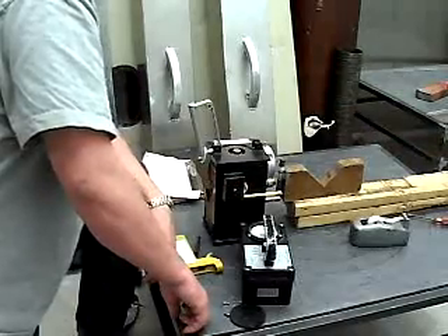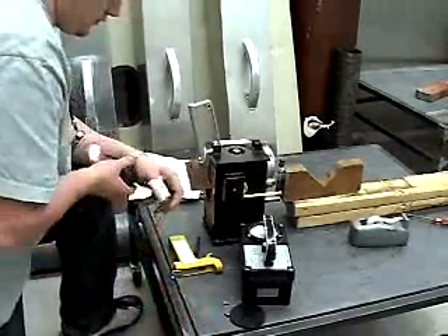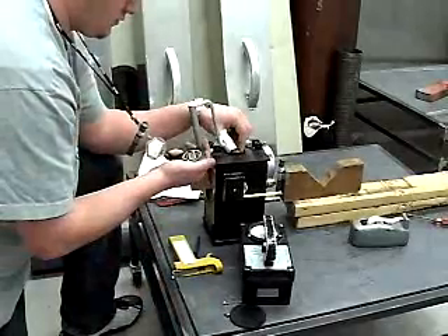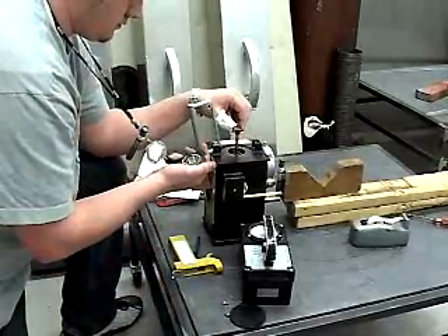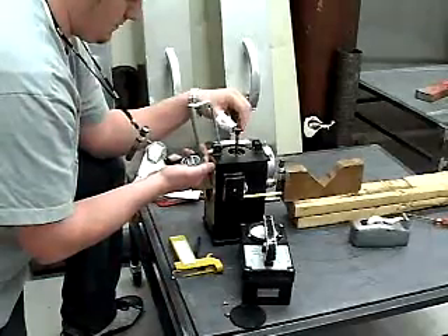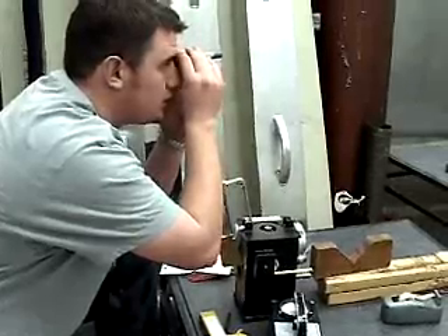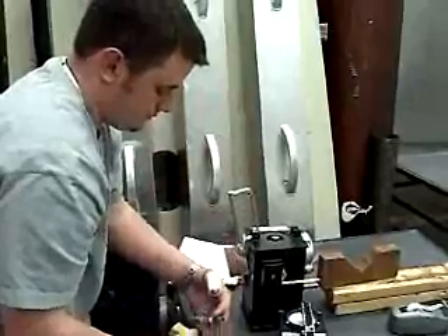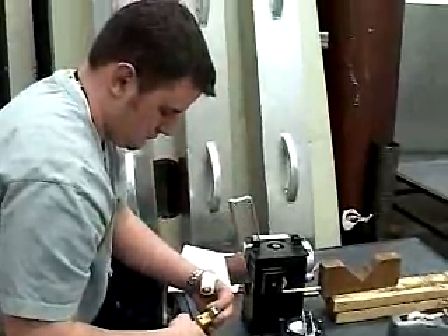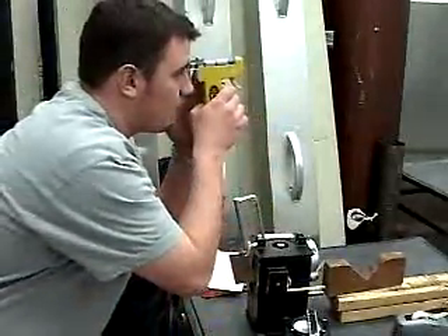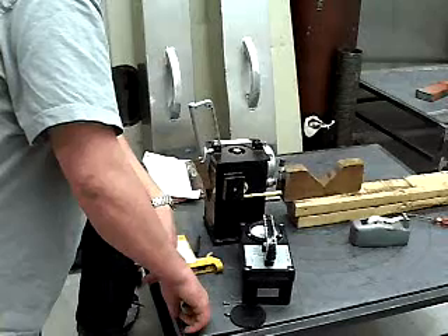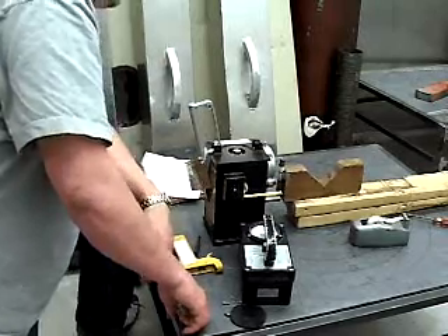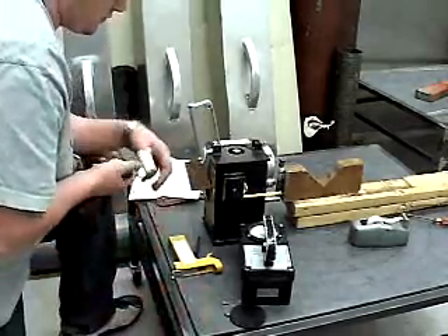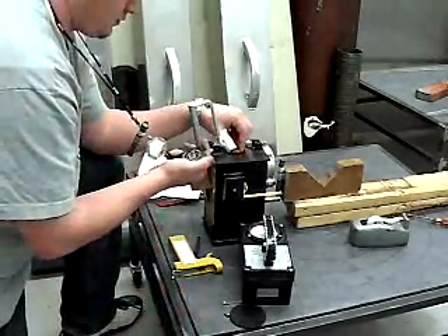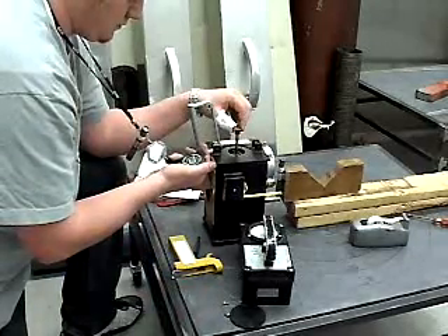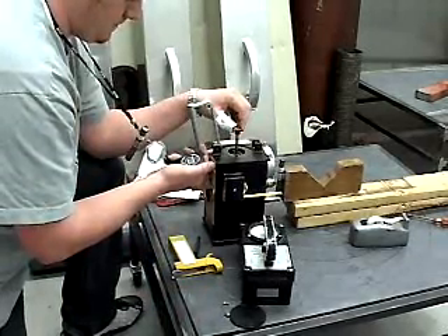The source is then exposed and the dosimeter is allowed to remain in the 3200 mR per hour beam for 45 seconds. This should produce a recorded dose of 40 millirem. The dose from the dosimeter is then read and recorded and the dosimeter is recharged. The dosimeter is then placed at the same distance in front of the calibrator source and exposed for 3 minutes. This should produce a recorded dose of 160 millirem.